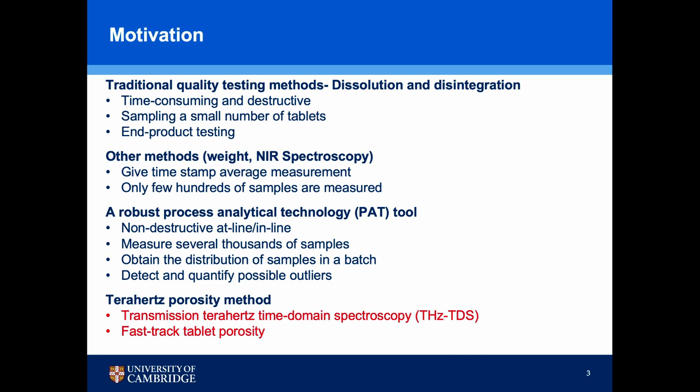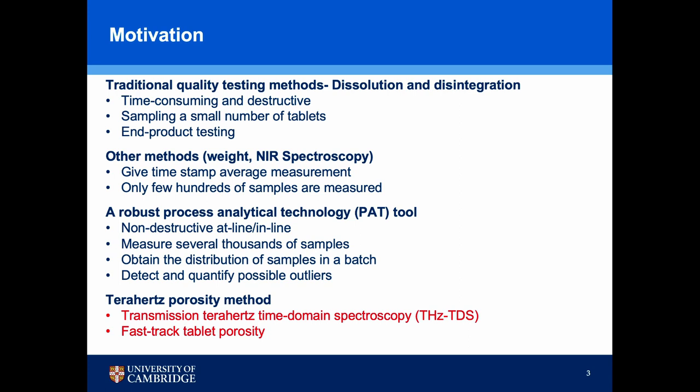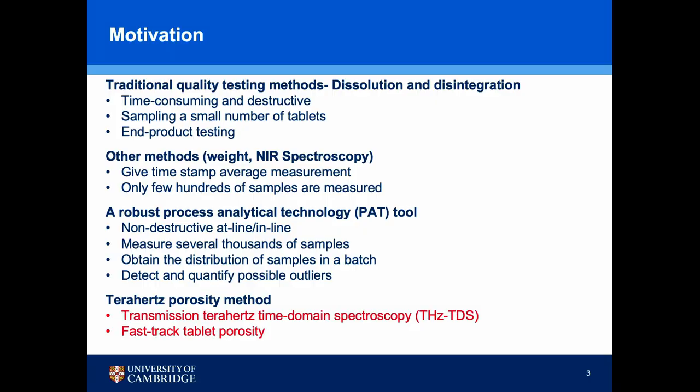Scientists have developed and adopted several of these methods. However, most of these methods give results based on a time stamp, meaning we only have average results within a certain given time, so we don't have access to the results for the individual tablets. We have developed a method based on Terahertz transmission measurements which can accurately predict dissolution and disintegration of pharmaceutical tablets. This method is very fast and non-destructive, and we are able to measure individual tablets and have a full distribution of the tablets, hence we can track possible outliers within a batch.